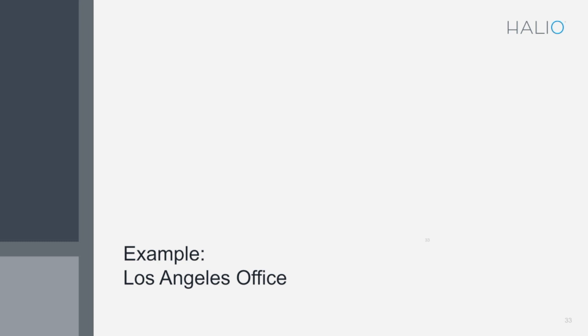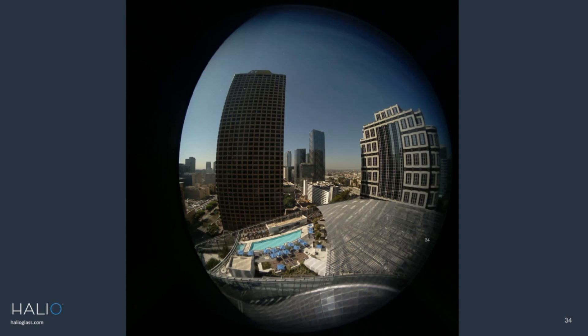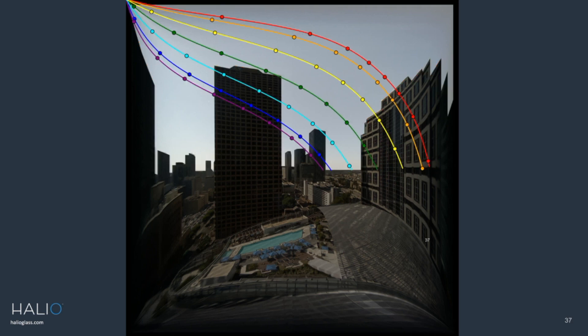This is a Los Angeles office building. You can tell it's LA because they've got a roof pool, not a cloud in the sky, and a band of smog along the horizon. Two images, one from each side of the window, are reprojected, traced, and then the sun path is overlaid to produce the map. For this one we had to use a full map. The facade was angled back by about two degrees, so the horizon is below halfway down the window. For skylights or windows angled backwards, we use a full square map, whereas for vertical or downward-angled windows, we can use a half map.